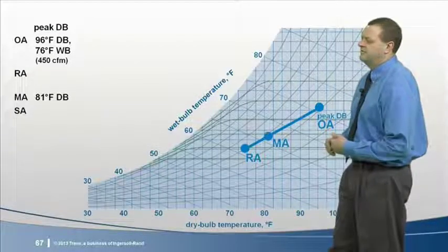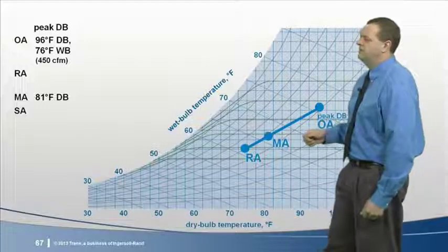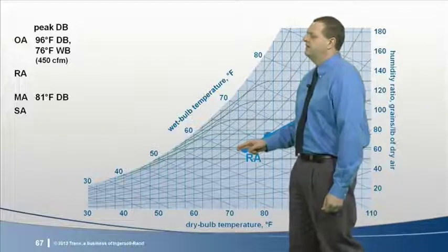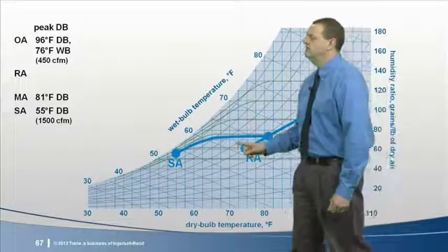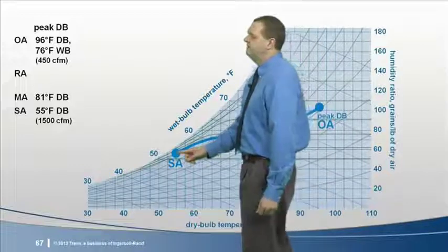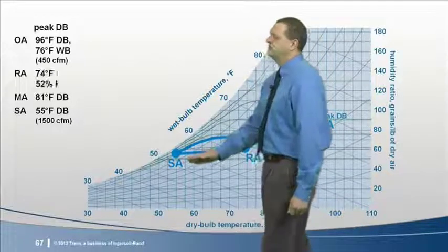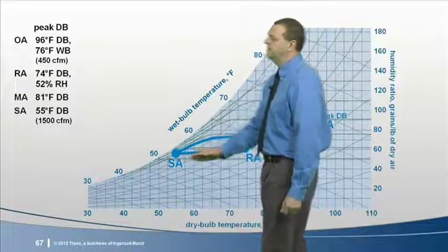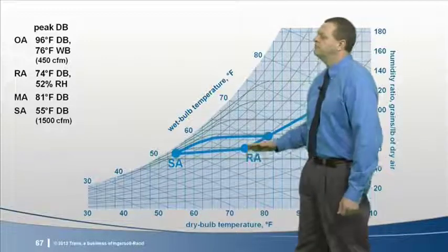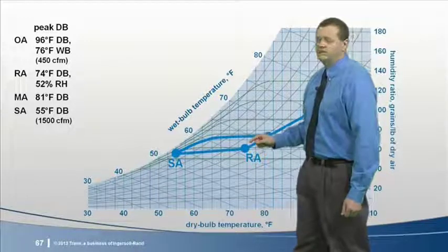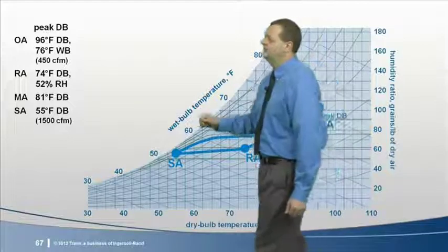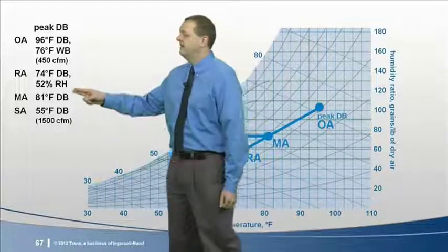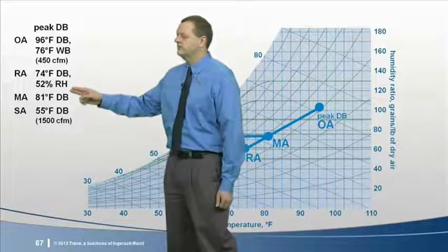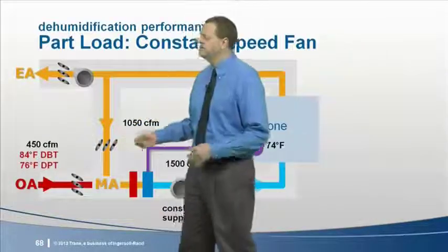Plotting this system on the psychrometric chart, the outdoor air mixes with the recirculated air. Then this mixed air gets cooled and dehumidified to about 55 degrees. This cool, dry supply air enters the space where it absorbs sensible heat and moisture. So for this example, the resulting relative humidity in the classroom is about 52% at design conditions. Now let's look at part load.